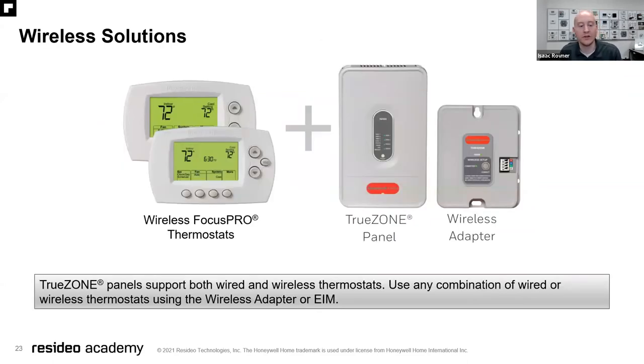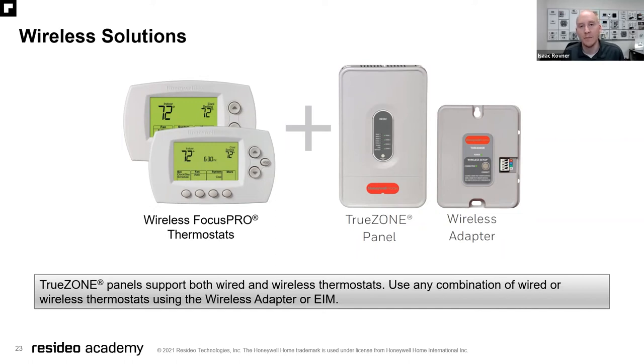A typical Redlink solution includes wireless Focus Pro thermostats, a true zone panel, and a wireless adapter. We can use the wireless adapter or we can use an equipment interface module — the EIM — and wire that to the thermostat side of the zone panel. We can mix and match: some thermostats can be wireless, some wired. You have the option to select which zones you want wired and which zones you want wireless.